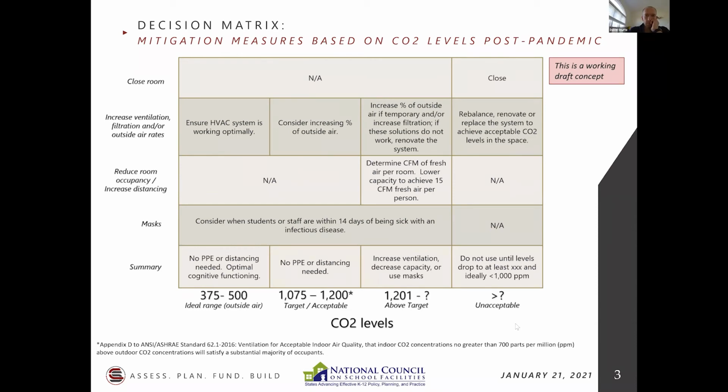Now, there's so much being sold on ionization, needlepoint ionization, bipolar ionization, etc. And ionization, historically, has not been as effective as we would like it to be with reducing particulate load in the air. And in addition, when you're generating those ions, it's very possible you're producing ozone if not designed properly.